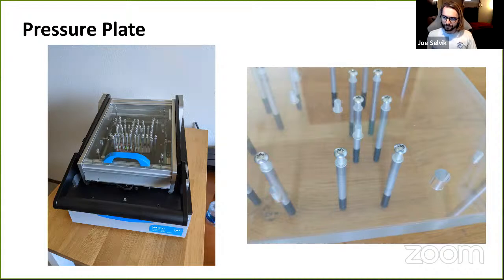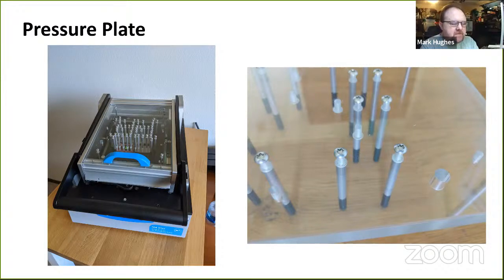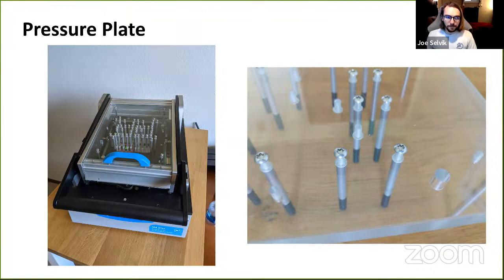So on a 75 mil on-center spacing, another word for pitch, what diameter test pin would you use for 75 or maybe even 50? I believe the minimum diameter of the test pad we support is 1 millimeter, or maybe 0.8 millimeters, but it depends on the tip style you want to use to contact that test point.